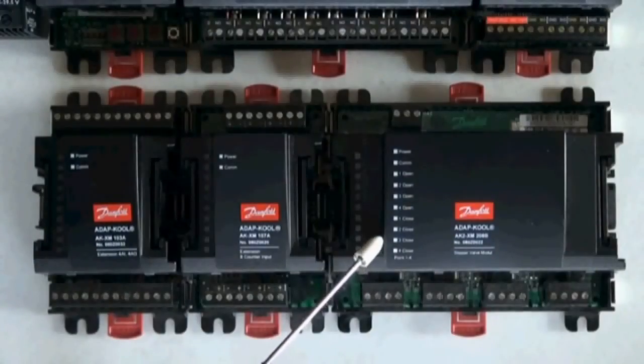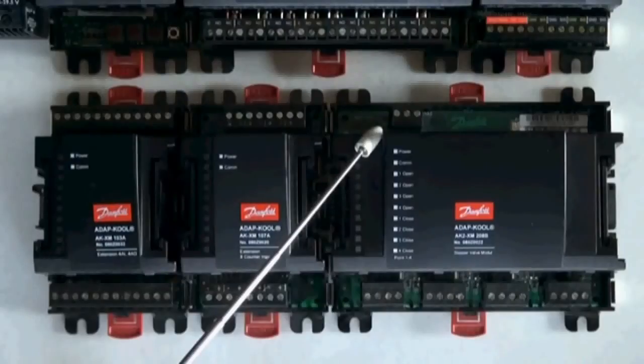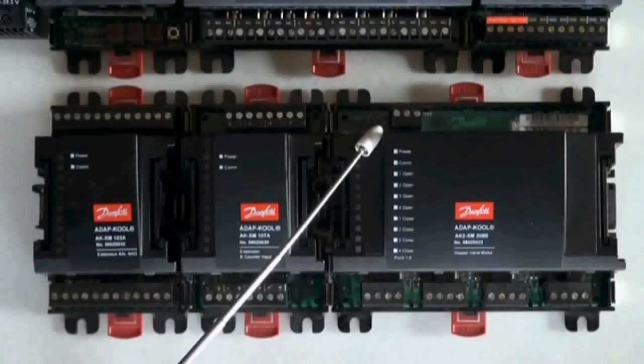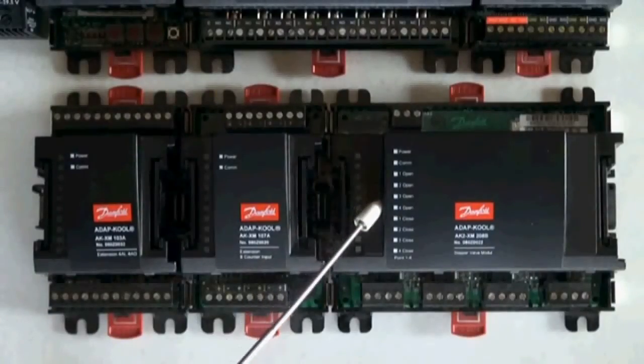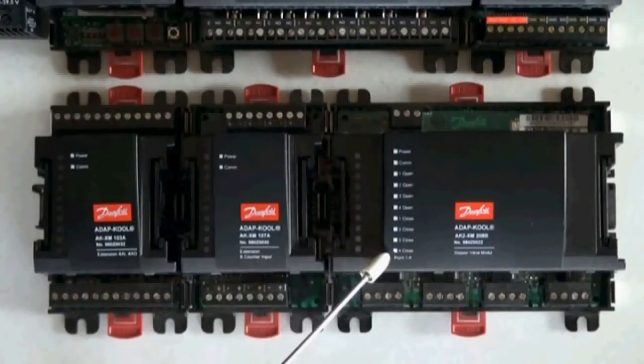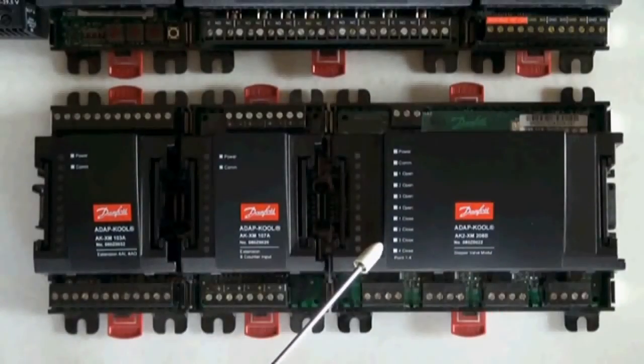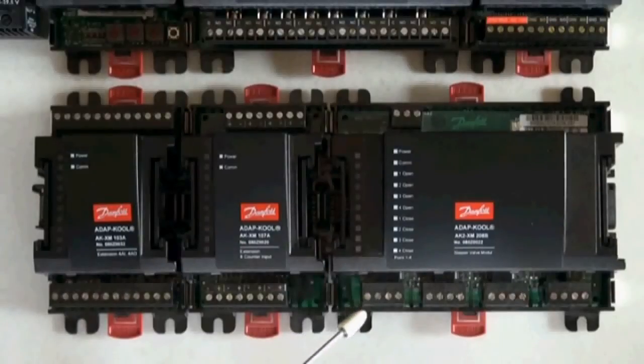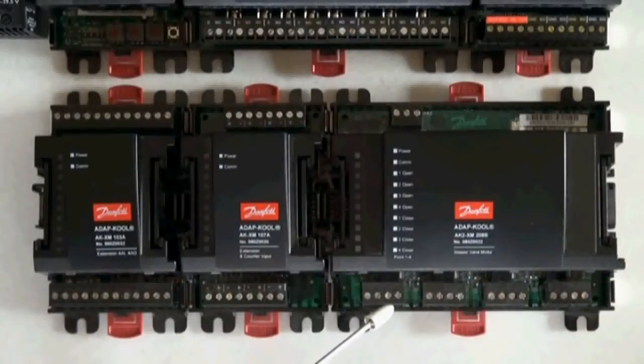And lastly, the stepper module. Power for the valves themselves is provided at the top. 24 volts DC or 12 volts AC will be wired here to power the valves. Indicator lights shown here will indicate if each valve is opening or closing. Connections to each valve are made here. Wire polarity is important. Consult the manufacturer's diagrams based on the valve you're using.